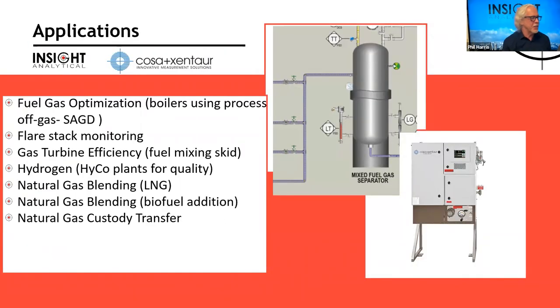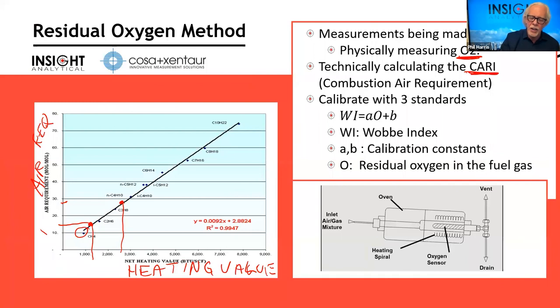Common applications where this goes: any place where people are trying to optimize their fuel gas. A lot of industries, whether it's a refinery, an operating natural gas plant, or heavy oil recovery, get what's called casing gas, or associated gas, that comes back with oil. Those things all have varying compositions, and so they need different amounts of air. If we go back and look at this chart, if my composition moves from here to here, well, I need a different amount of air going to my burner.